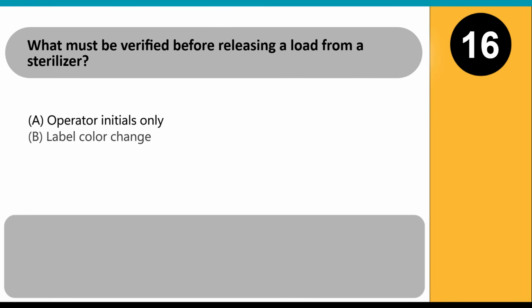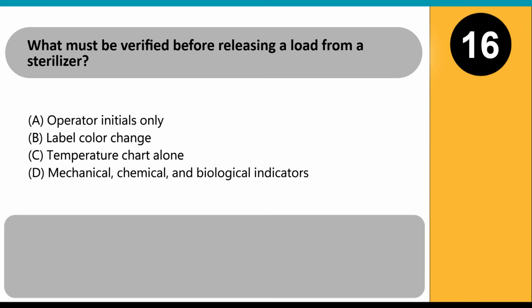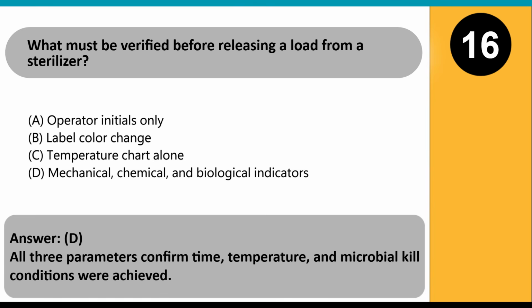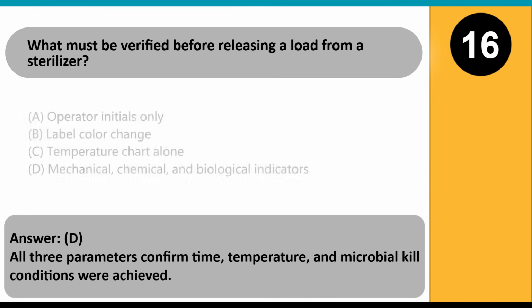What must be verified before releasing a load from a sterilizer? A. Operator initials only. B. Label color change. C. Temperature chart alone. D. Mechanical, chemical, and biological indicators. Answer: D. All three parameters confirm time, temperature, and microbial kill conditions were achieved.